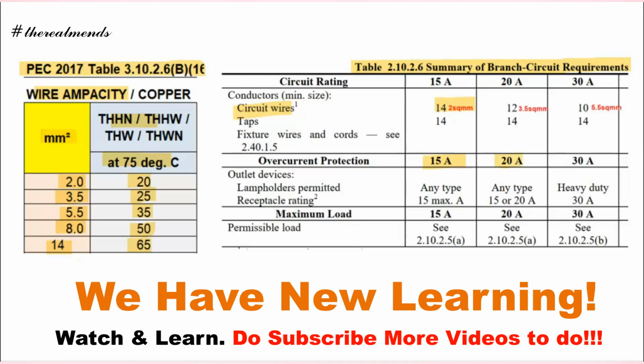Pag 20 ampere trip, so minimum is 3.5 square mm or number 12. Pag 30 ampere trip, so yung circuit wires mo is 5.5 square mm. So ito yung gamitin natin, itong table ng capacity, also itong table ng branch circuit requirements.